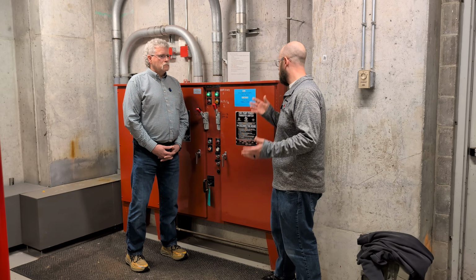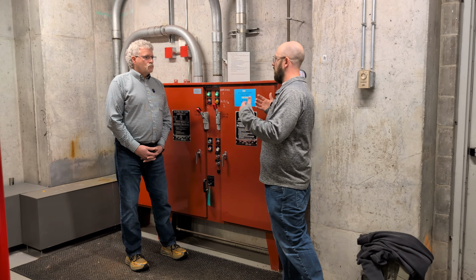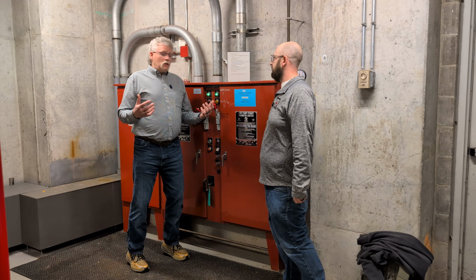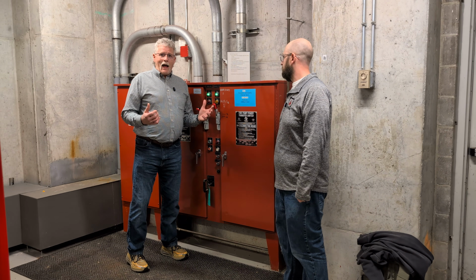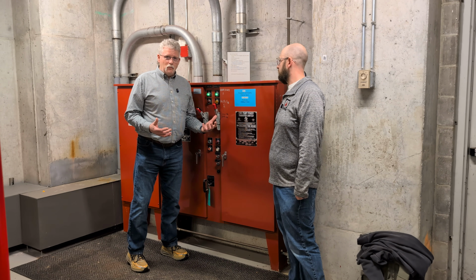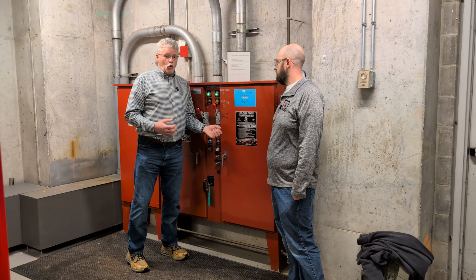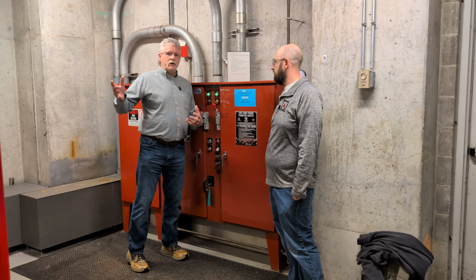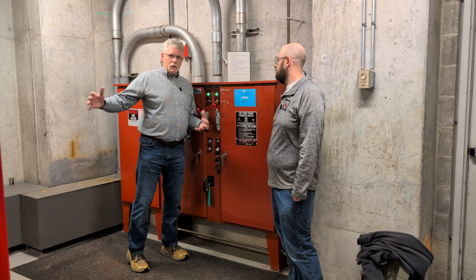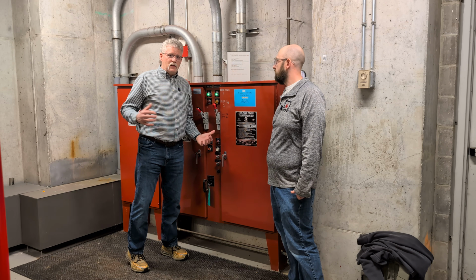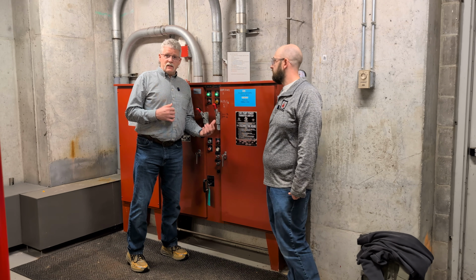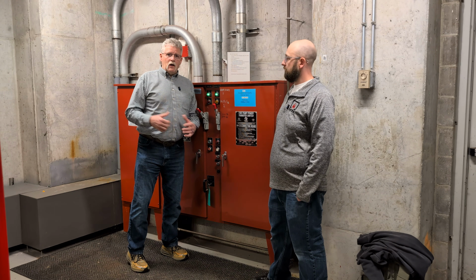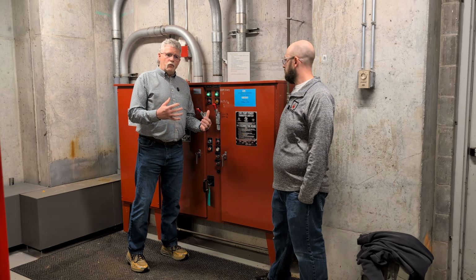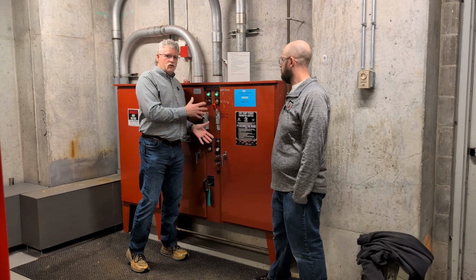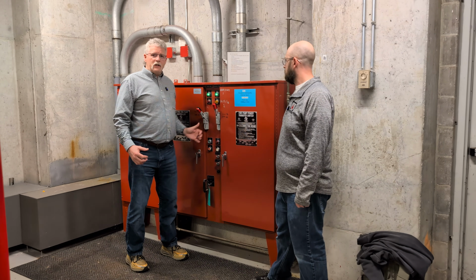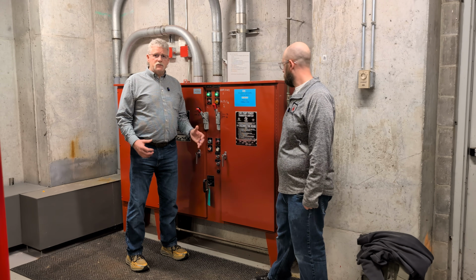Now, how would we provide an alternate source of power? How is it usually done? Frequently, the alternate source of power is an on-site generator sized according to the locked rotor current, and possibly even the jockey pump, depending on whether that's connected in with the pump controller. In this example, we have a separate fire pump controller, and so the fire pump itself is controlled from this. And so it's a combination disconnect and transfer switch.